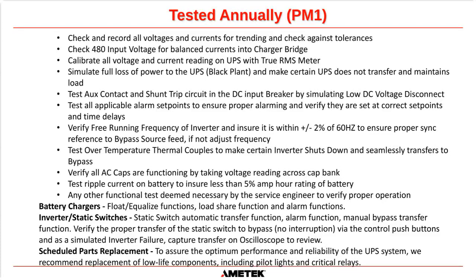We also test the aux contacts and shunt trip circuits to make sure that the DC input breaker trips at the correct voltage. And that voltage for a 60-cell battery is usually 105 volts. So we want to make sure that the protection is in place if the battery goes below 105 volts, that breaker is tripped so we don't over discharge the battery and basically ruin the battery, and therefore you would need to buy a new battery.